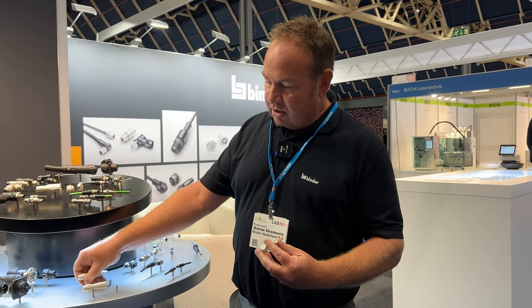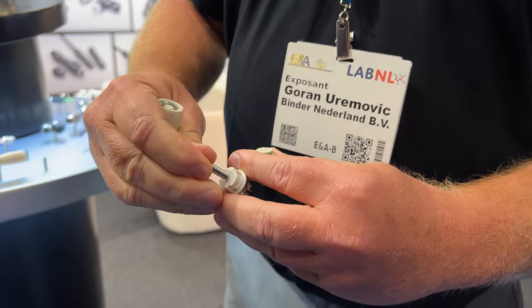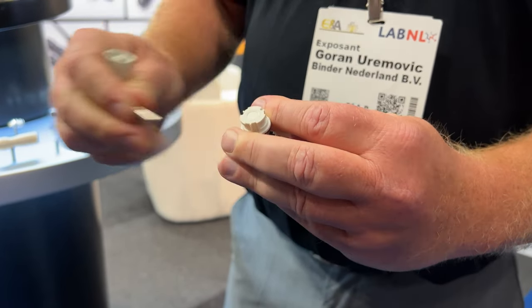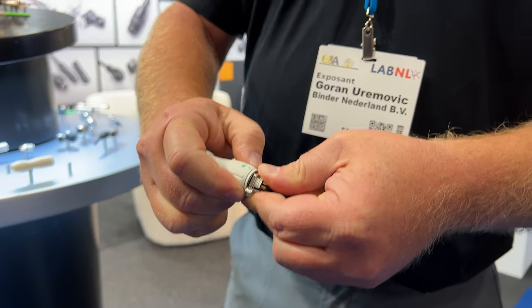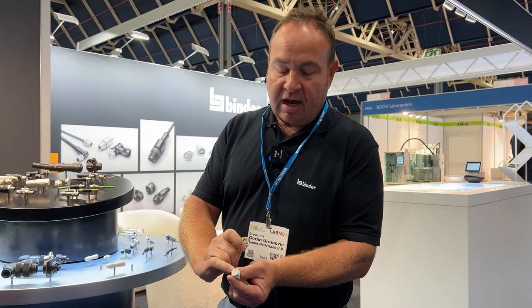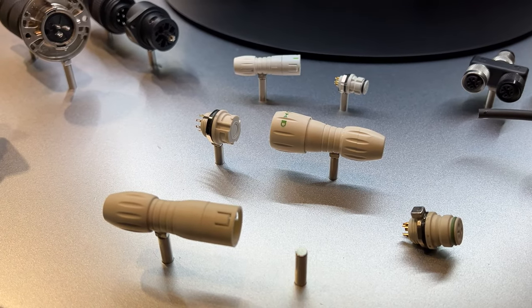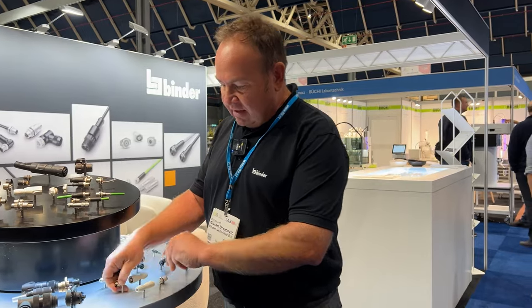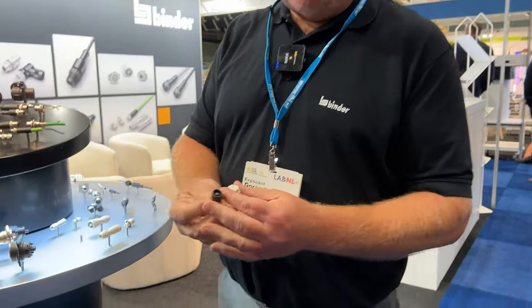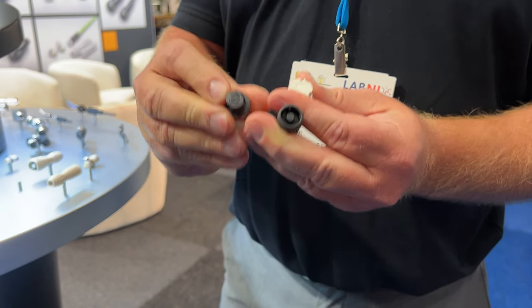When you take the mating part and push the two pieces together, there is a spring inside that goes inward, opening the connector so you can connect the two parts with a bayonet locking system. When you disconnect, the cap comes back out and restores the IP67 protection. The material is PA plastic — the same as standard connectors. This same NCC system is also available for sub-miniature connectors, providing IP67 protection in unmated status.